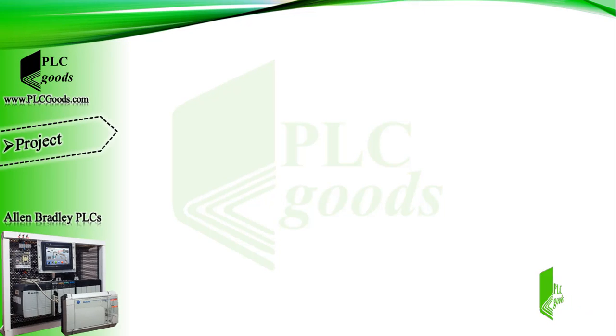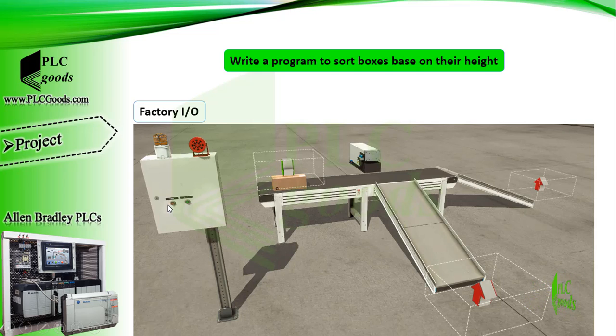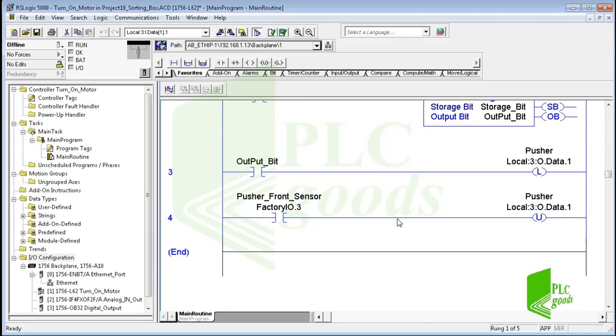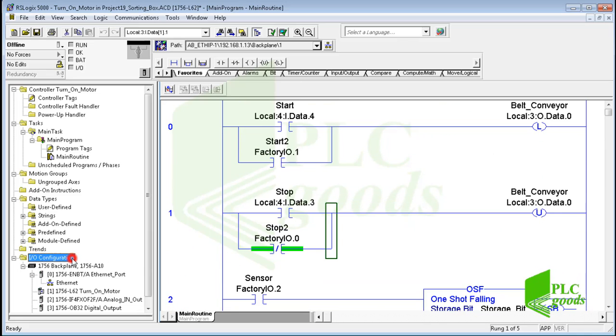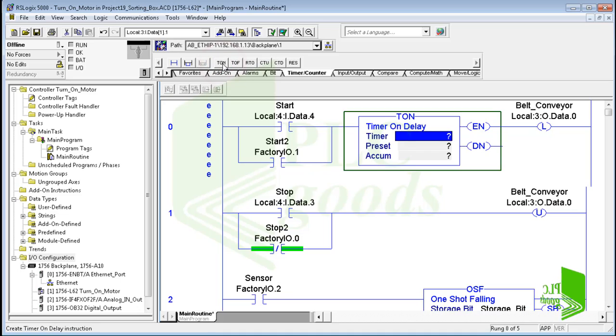Now let's do a simple project using Factory IO software. If you remember, we did the sorting box project in the previous video — now I want to modify it using timers. In this project, if I press the start push button, first the siren alarm should activate for five seconds; after that the belt conveyor and warning light will start. Also, if I press the stop push button, the belt conveyor must be stopped after 10 seconds to move all boxes which are on the belt conveyor. Let me insert an on delay timer and use its done bit to turn on the belt conveyor after five seconds.